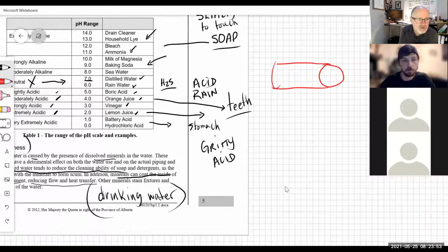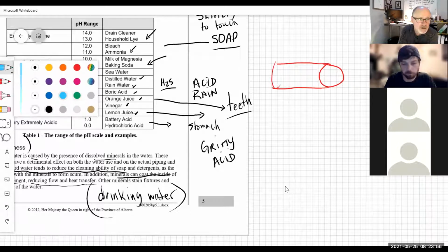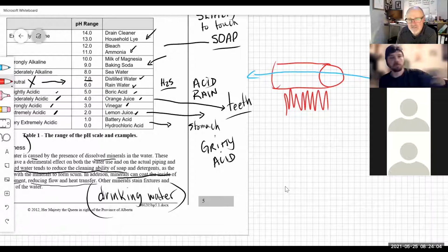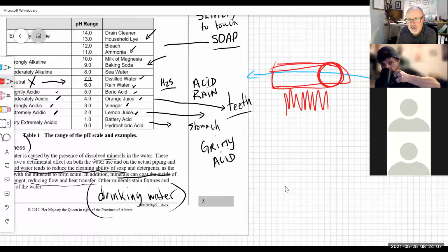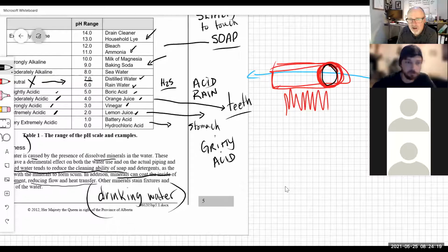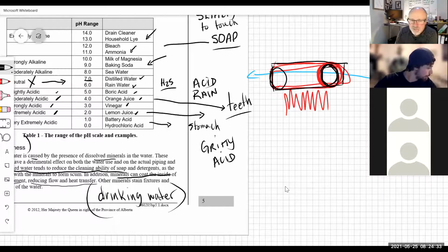When we have water flowing through these, you have the flames hitting these very thin heat exchangers, and as the water flows through, as it heats up, it will coat the inside of these pipes with this hard water. And what happens is you don't get the heat transfer through that little heat exchanger, right? Because you will have a coating inside there.